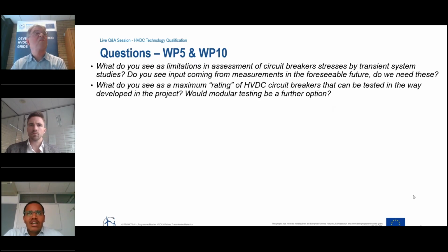If I just look at this method from the perspective of KEMA laboratories, we could put together a lot of components in series, and we might be able to test HVDC circuit breakers up to 500 kV. That means our components can handle the TIV coming from the breaker up to 800 kV. So those are the two challenges that you have to consider when thinking of testing an HVDC circuit breaker in the method proposed.